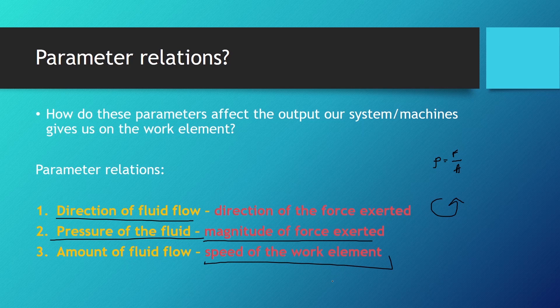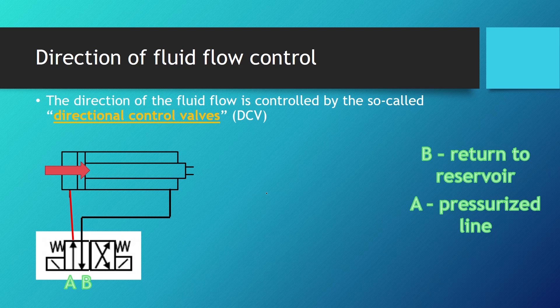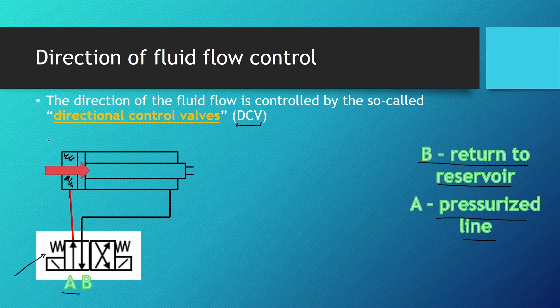Let's look at some examples for each parameter. The direction of fluid flow is controlled by directional control valves, or DCVs. Here is the schematic for a directional control valve, which is intuitive with arrows pointing at the direction of fluid flow. Line A is the pressurized line, and line B is the return line that goes back to the hydraulic reservoir. In this position, the pressurized fluid is getting to the front of the piston, filling up and pushing the piston and piston rod to the right side — in other words, extending the hydraulic cylinder.